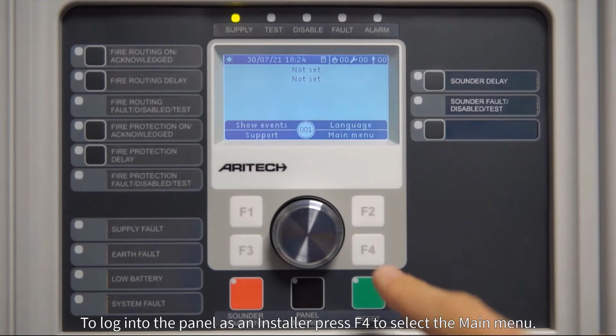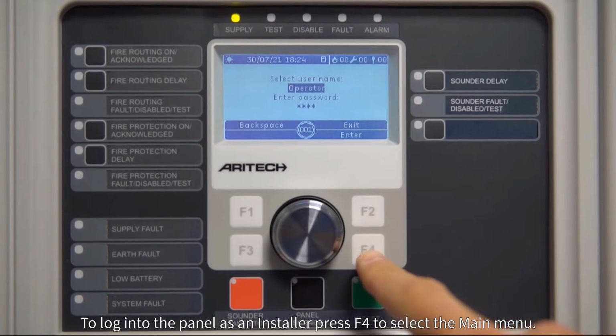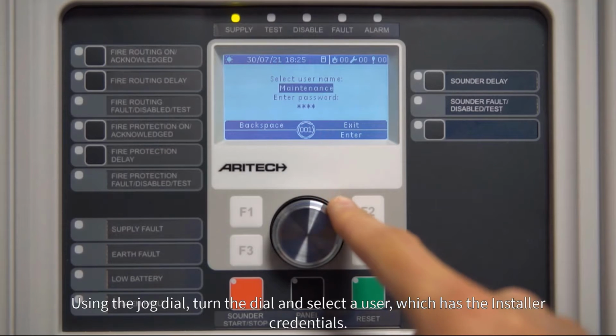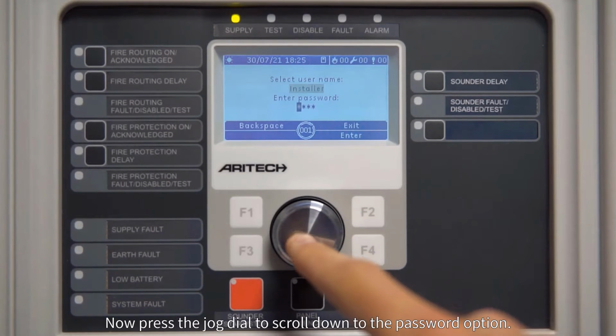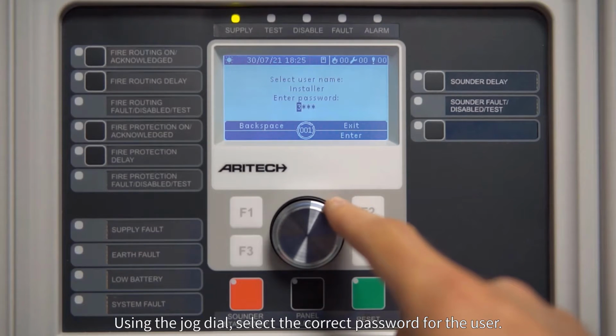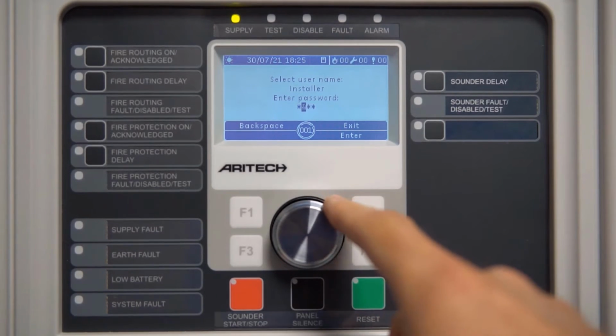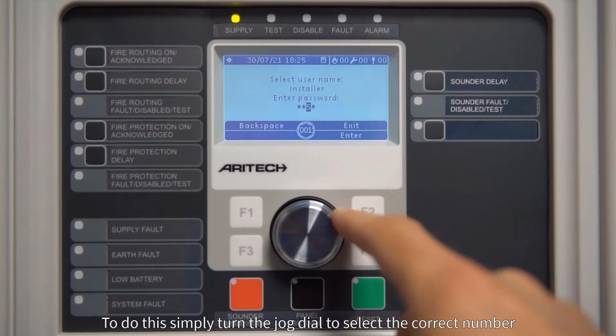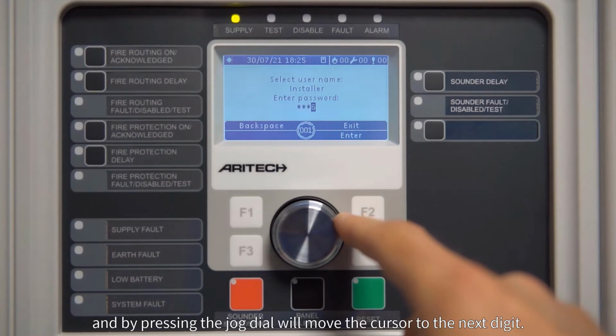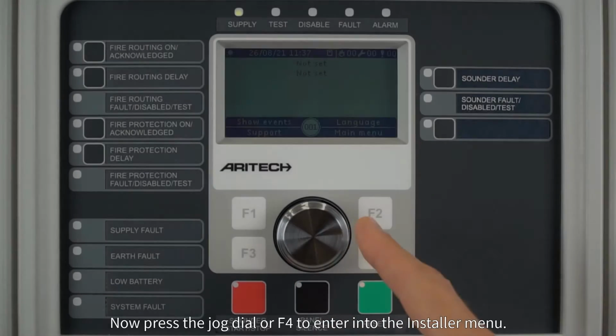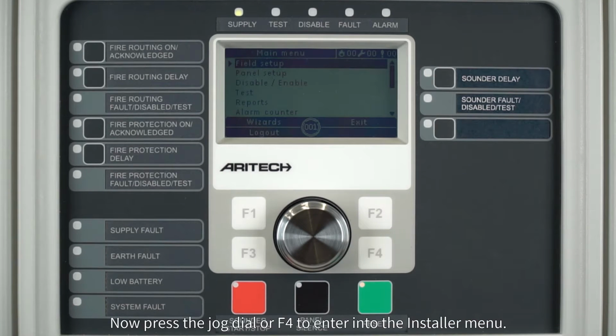To log into the panel as an installer, press F4 to select the main menu. Using the jog dial, turn the dial and select a user, which has the installer credentials. Now press the jog dial to scroll down to the password option. Using the jog dial, select the correct password for the user. To do this, simply turn the jog dial to select the correct number, and pressing the jog dial will move the cursor to the next digit. Now press the jog dial or F4 to enter into the installer menu.